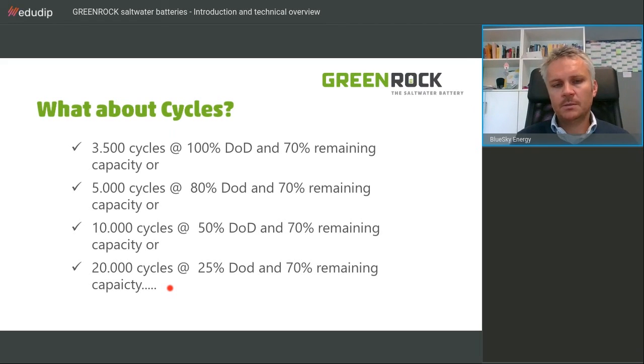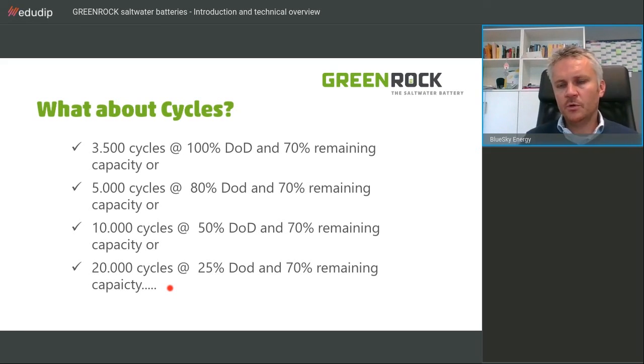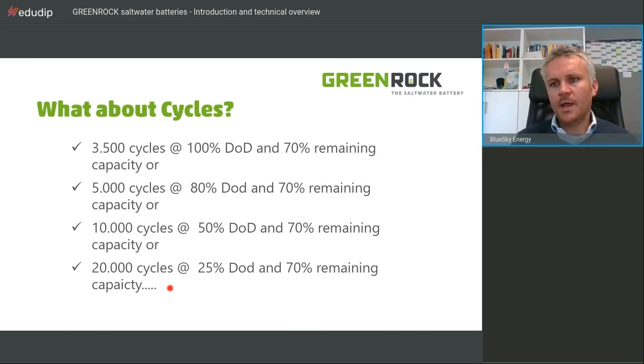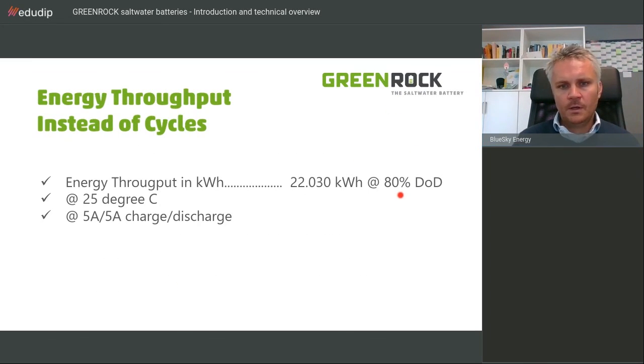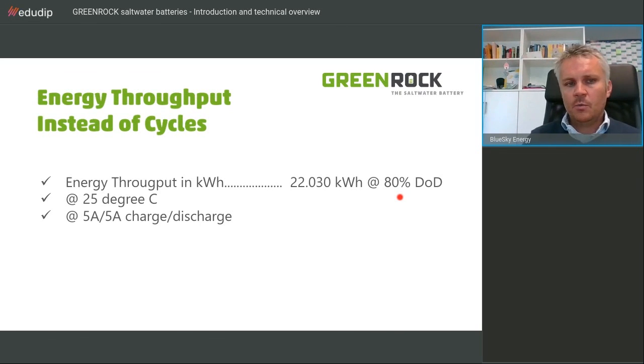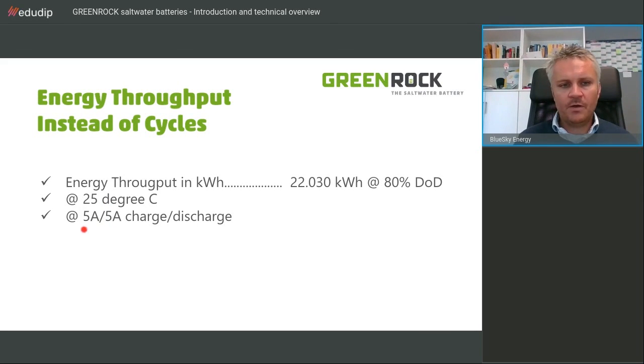In this case, it's the factor depth of discharge. So when you are benchmarking battery technologies for your installations, for your projects, please take that into account to compare apples to apples. And in a perfect world, when we have 25 degrees centigrade, 5 amps charge discharge, we bring 22,030 kilowatt hours at 80% DoD out of that battery, which is a very good output. But of course, in reality, we won't see those lab situations all the time, because temperature varies, the depth of discharge varies, and the charging currents, of course, vary as well.